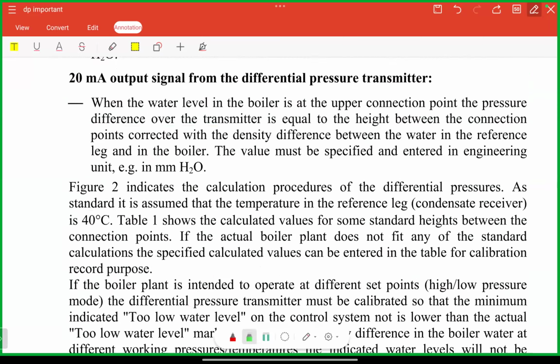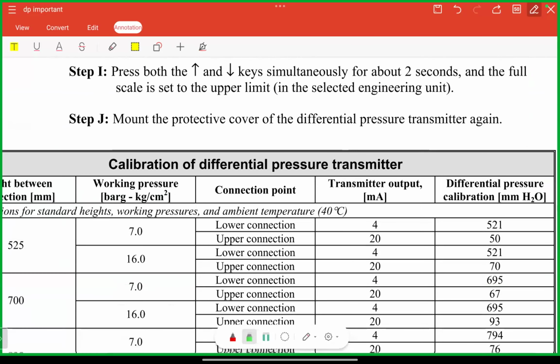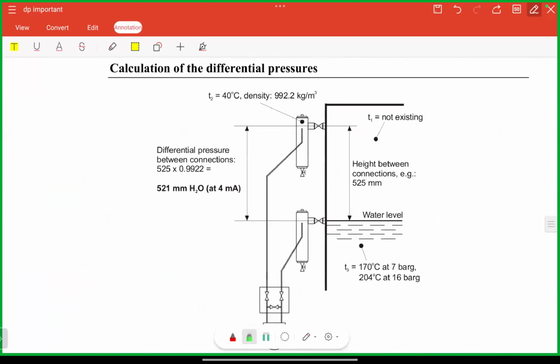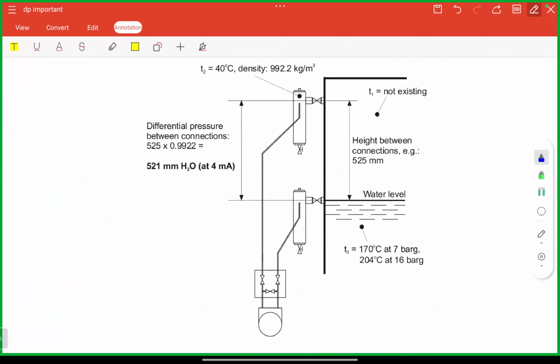So for the same purpose, let's look at here. Okay, this arrangement here. Now in this arrangement, please look into the temperature and density. Right now, we are calculating for 7 bar pressure. Okay. We are calculating for 7 bar pressure. We are assuming that the ambient temperature of the engine room is 40 degrees. Corresponding to 40 degree temperature, the density is 992.2 kg per meter cube. Okay. So we have to calculate the difference. So let's assume that your water level is low, and then we are going to calculate the difference in pressure.